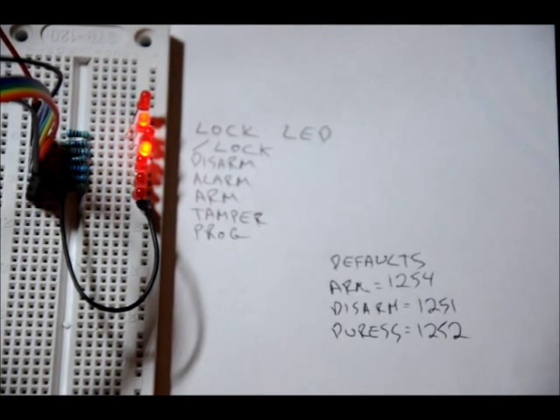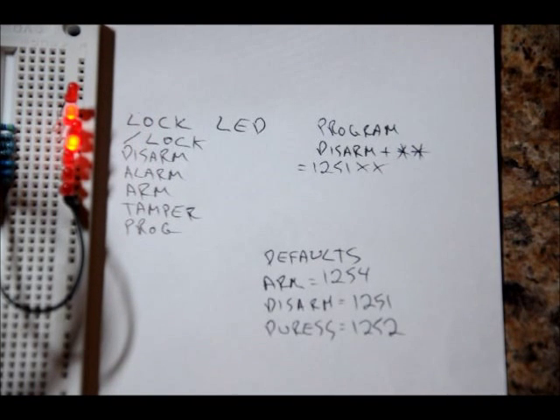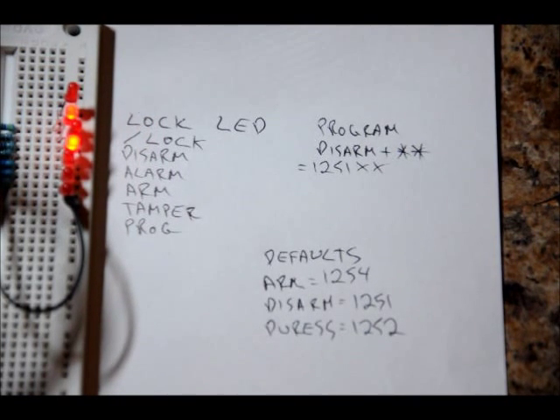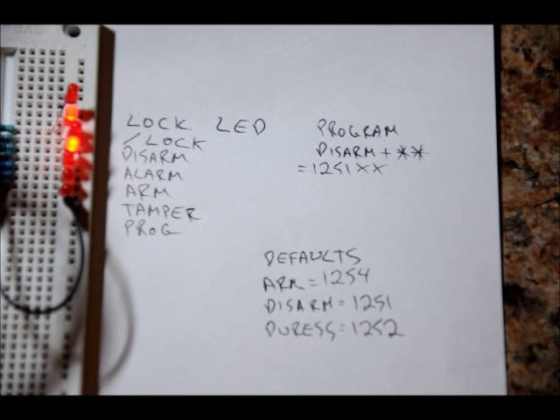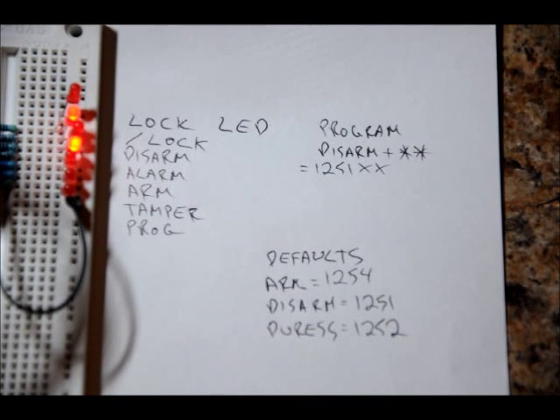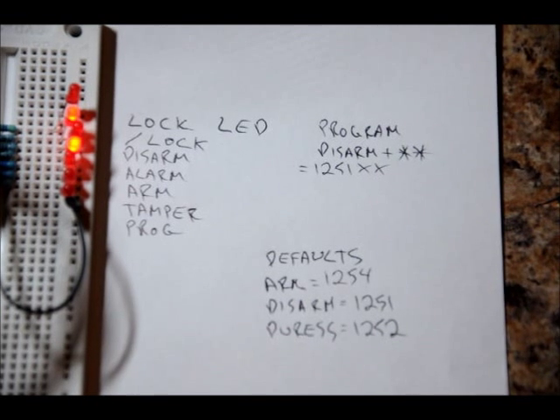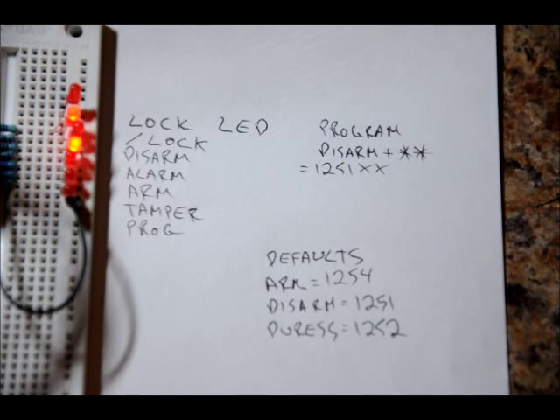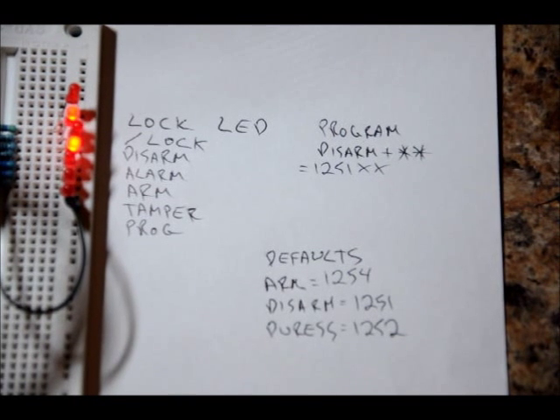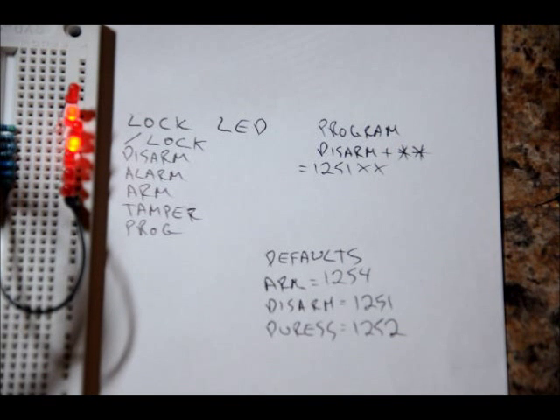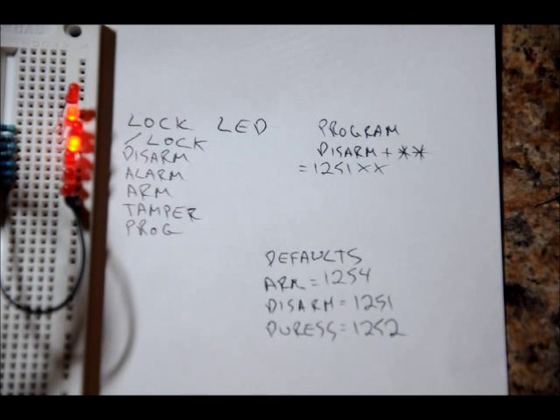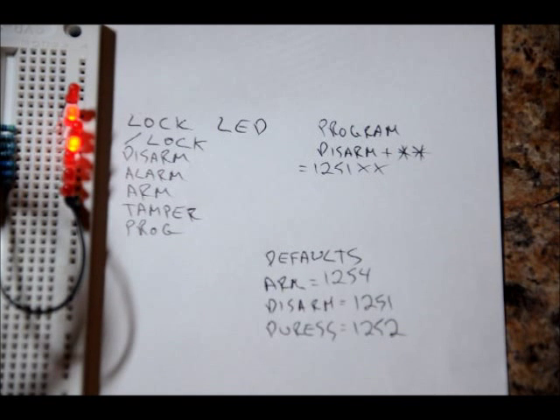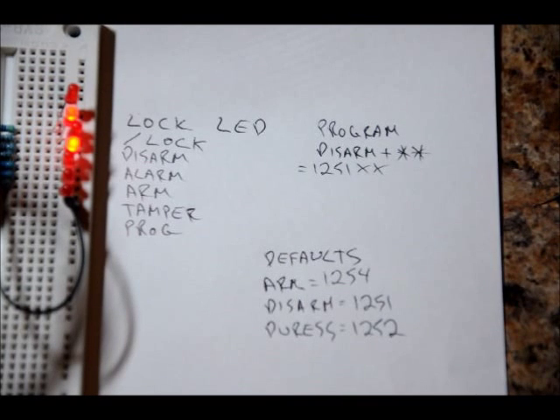Now let's talk about program mode. To enter into program mode, you have to press the current disarm code plus star star. In the case of our default codes, that would be 1-2-5-1 star star. Disarm is 1-2-5-1. Now we basically have to use six, we have to create a sequence of six numbers or letters. By the way, the numbers go from zero to nine. The characters are star and number sign, and the letters are A to D on the right. We have to program into our three new codes because we need a new disarm code, a new arm code, and a new duress code.